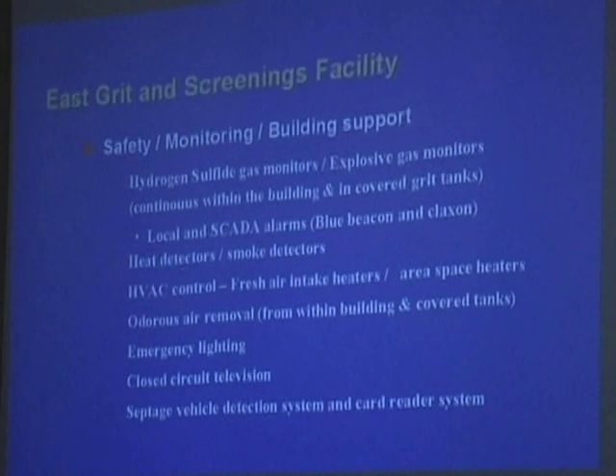So if you do get either an explosive gas condition or hydrogen sulfide buildup from bringing wastewater through the facility, we will be notified of that. There's heat detectors and smoke detectors throughout the building. I'll point some of those out as we go through. HVAC control has not, I believe at this point, been set up as of yet. That monitors or controls your fresh air intake as well as your space heaters.